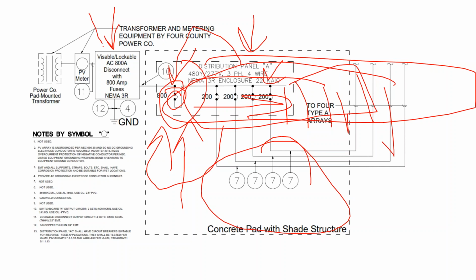And then the utility came in and said, we are going to require, it was kind of funny on this ground mount, it was a 1600 amp ground mount. And the utility said, well, we have this knife switch disconnect requirement. But knife switch disconnects only go up to about 800 amps, and then they're 6 feet tall and look kind of ridiculous. There wasn't a 1600 amp knife switch disconnect. At that point, you get into big boy electrical equipment, and you might have just a main switch that's not a knife switch.